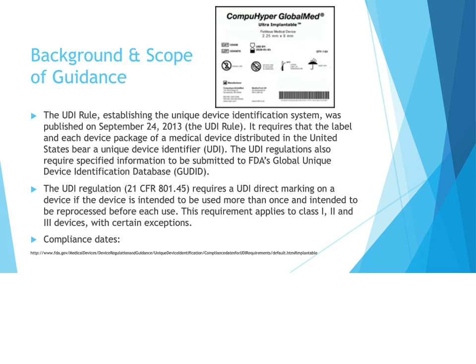So what is direct marking? It means that you affix the UDI permanently to the device itself through etching, attaching a permanent plaque, or affixing a permanent tag such as an RFID to the device. It is FDA's belief that because these devices are intended to be reprocessed and reused, it is likely they will be separated from the original labels and packaging. Direct marking will help ensure identification of these devices throughout their life cycle.